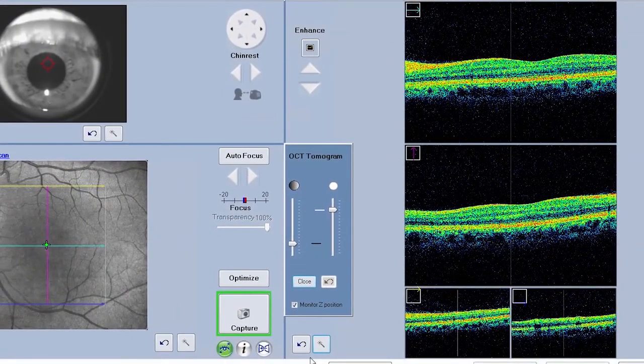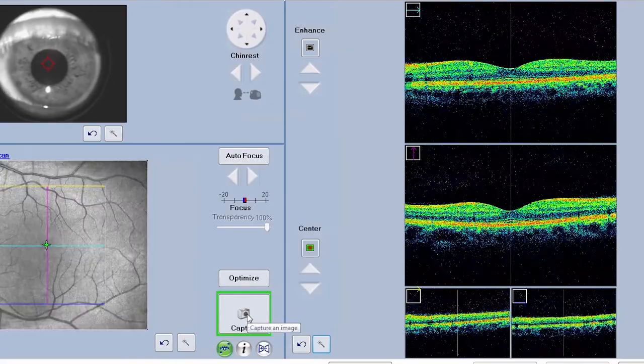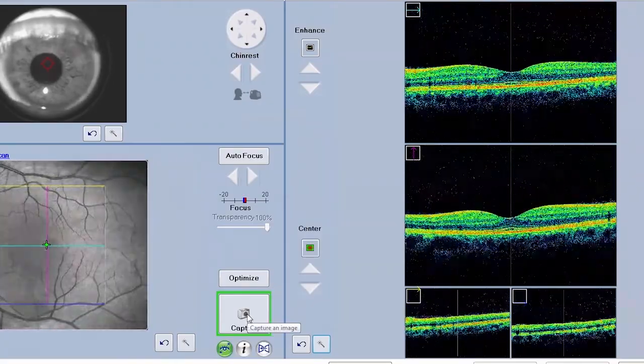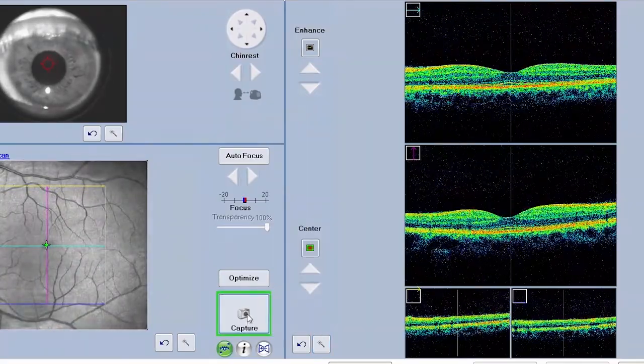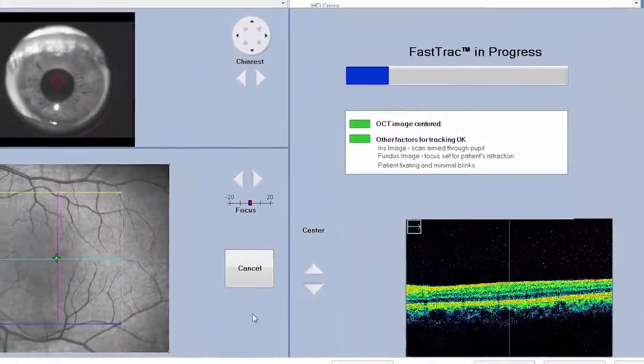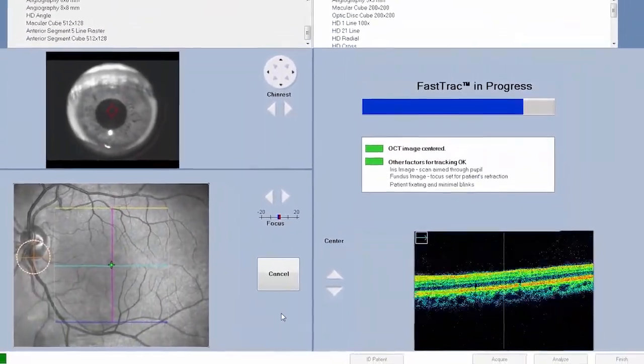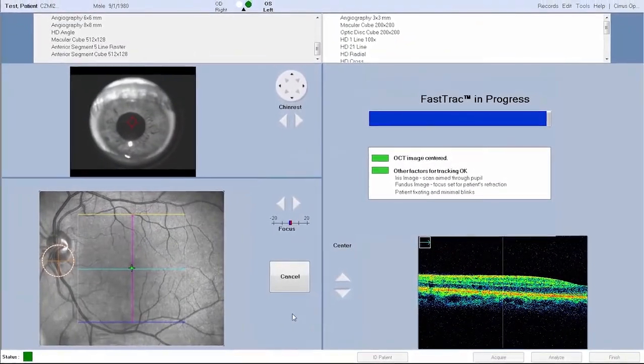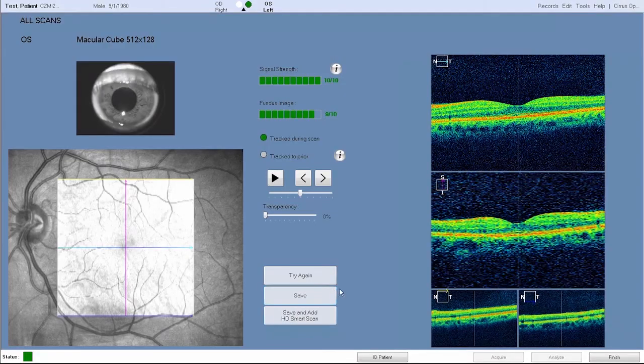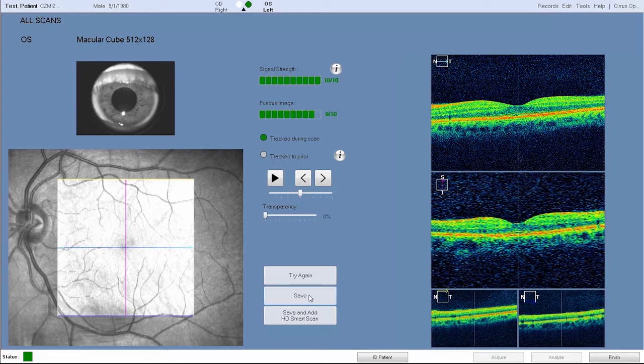After you have satisfied all previous steps in acquiring a quality scan, click capture. A review screen will appear when a scan is acquired. If the captured scan quality is acceptable, click save and return to the acquire screen if you wish to capture another image.